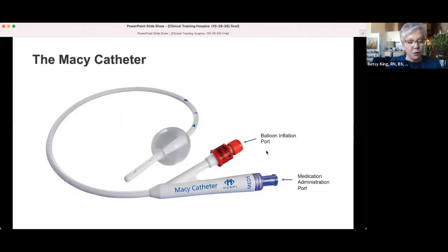The balloon inflation port works exactly like the balloon inflation port on a Foley catheter. This is where you're going to attach a Luer-Lock syringe and inflate the balloon of the catheter once you insert it. On the hub here, it says inflate with 15 mils, and that's just a helpful reminder for you as to how much to inflate the balloon with once you've inserted. This port can only be accessed with a Luer-Lock syringe. So there is a built-in safety feature there. Families cannot accidentally inject the patient's medicine into the balloon of the catheter because the syringes will not fit on each other's port.